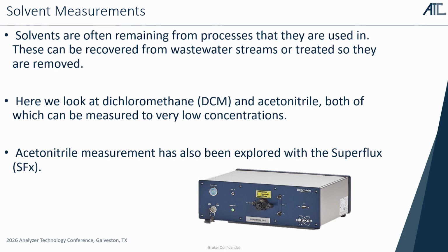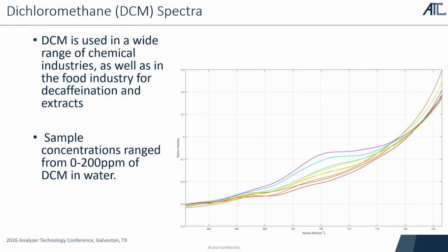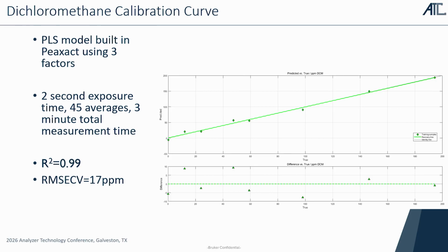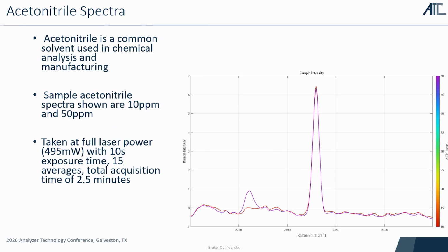All right, so DCM, acetonitrile, solvents that are commonly found, again, in wastewater streams, can easily be measured. You can see the separation there, and we're going from 0 to 200 ppm in these. So we're using 2-second exposure times, 45 averages, and we get a very good R-square and a very low error cross-validation. That's all the way down to 0, and this one was taken, let me see. Okay, so 10 ppm and 50, right? So these acetonitrile.